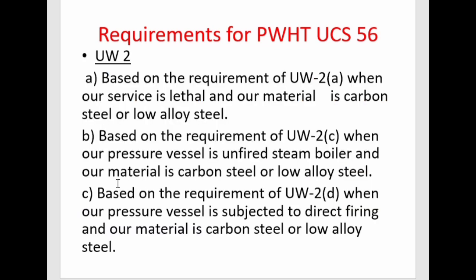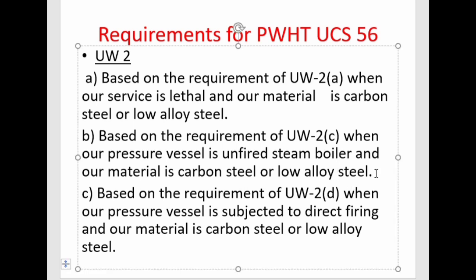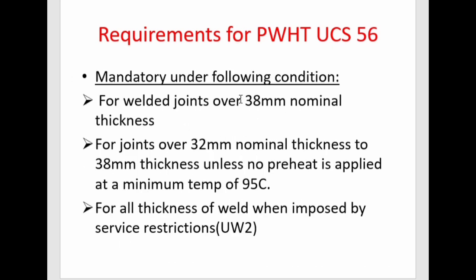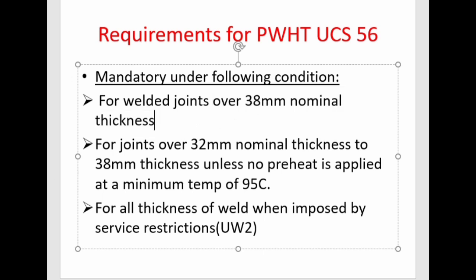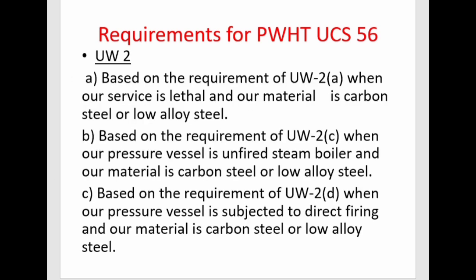The second case, based on UW-2C, is when the pressure vessel is an unfired steam boiler and the material is carbon steel or low alloy steel. The third case, based on UW-2D, is when the pressure vessel is subjected to direct firing and the material is carbon steel or low alloy steel. These are three cases requiring PWHT irrespective of the nominal thickness of the base material.